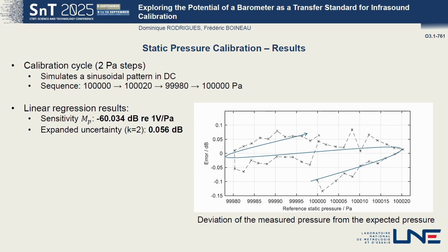So here are normally the results for the static pressure calibration. The calibration cycle was performed with 2 Pascal steps, starting from 1,000 hectopascal, increasing by 20 Pascal, decreasing by 40 Pascal, and coming back to the initial static pressure. So this simulates a sinusoidal pattern, but of course here in DC. The linear regression leads to a sensitivity of minus 60.034 dB with an expanded uncertainty of 0.056 dB in this case.